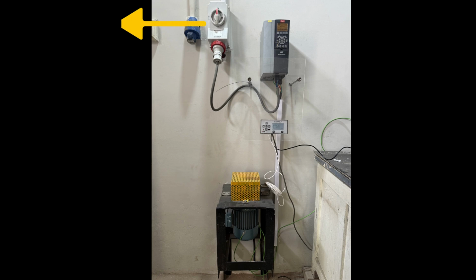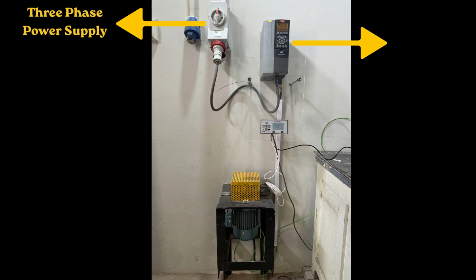This training module consists of a 3-phase power supply which provides electrical power to the VFD. The VFD controls the speed of the motor by varying the frequency. By adjusting the VFD frequency, we can simulate different rotating speeds. The acrylic sheet provides insulation and protects against the 3-phase power supply, preventing accidental touch while allowing visibility.